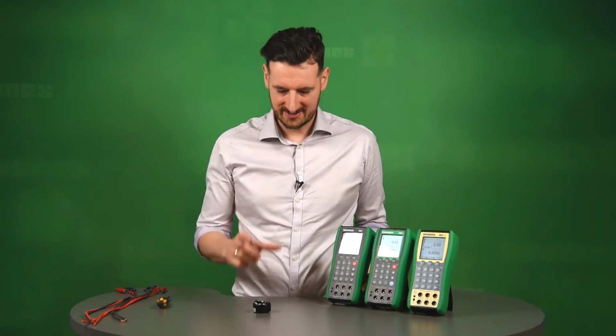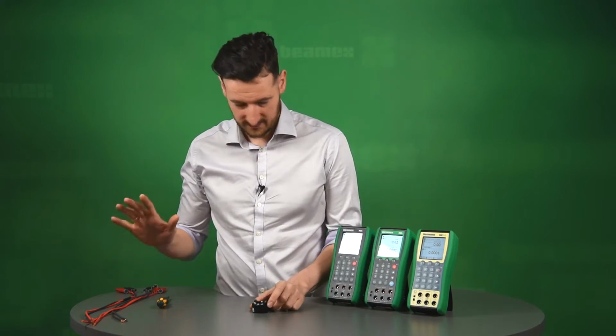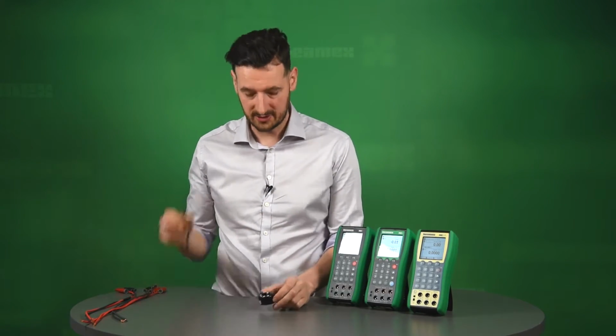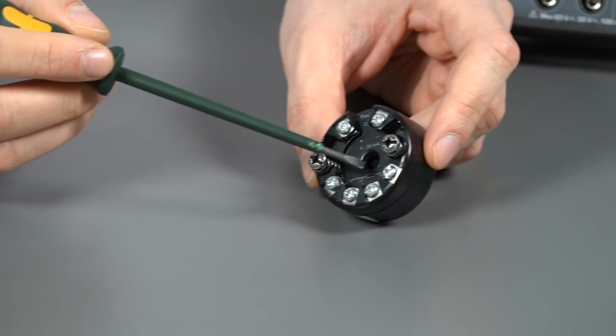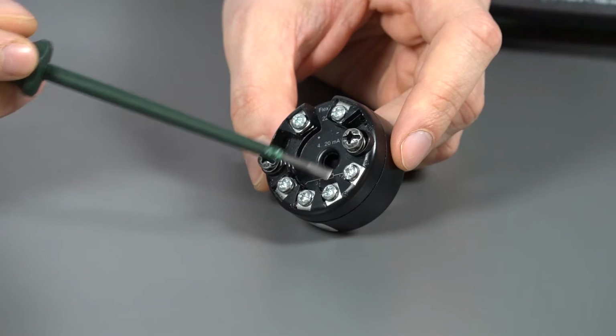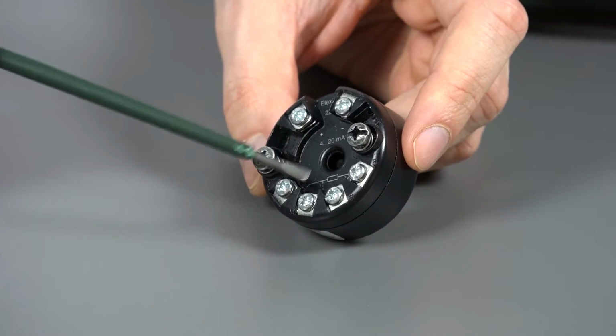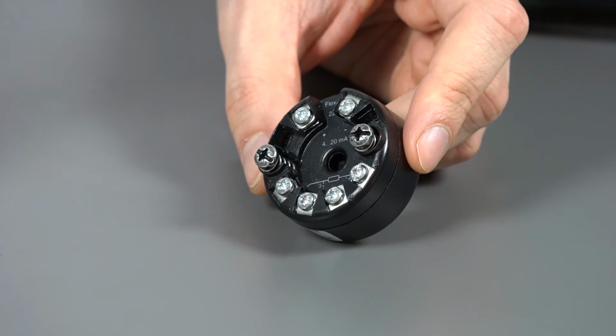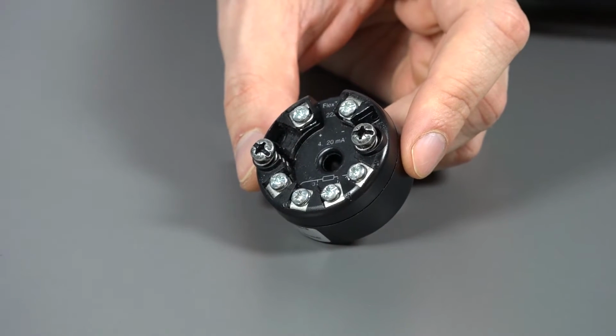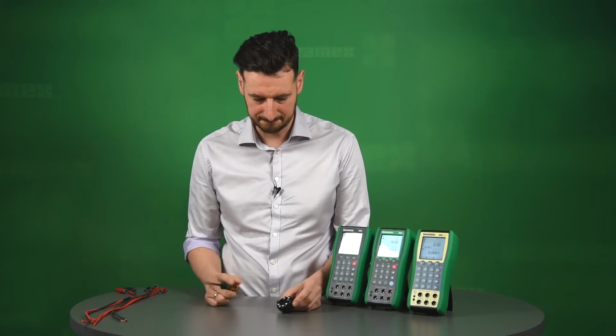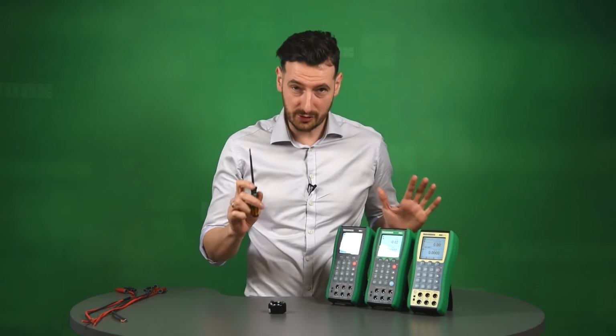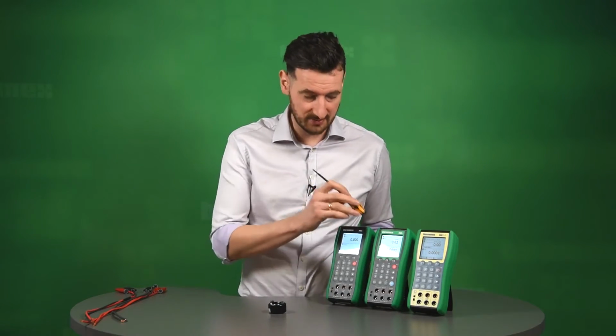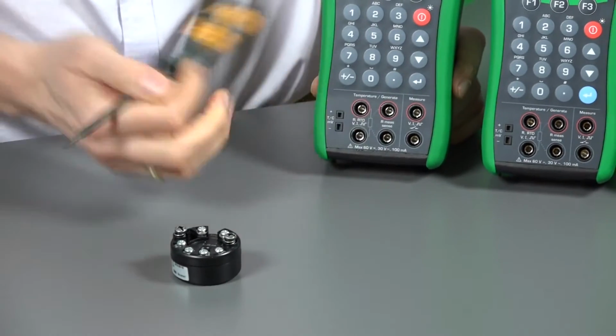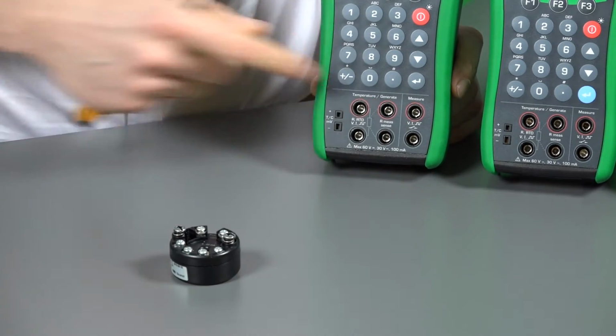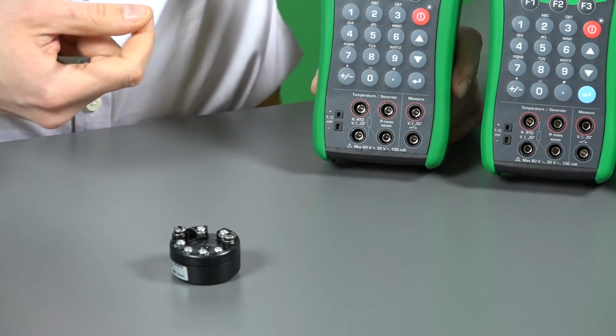What we're going to do now is calibrate this RTD temperature transmitter. I've got some test leads. We're going to connect them to our calibrators, but let me show you quickly how we're going to do that. You can see there is a resistor here. We're going to connect a 4-wire RTD on both sides of the resistor, and of course we're going to also power the transmitter using our units and measure 4 to 20. On our MC2 and MC4 family, you would go here on the RTD part, and you would go also here to measure the milliamps and power up the loop.